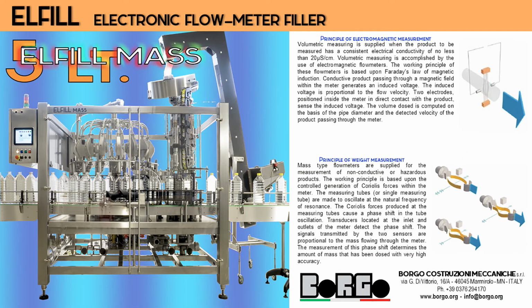Principle of electromagnetic measurement. Volumetric measuring is supplied when the product to be measured has a consistent electrical conductivity of no less than 20 microsiemens per centimeter. Volumetric measuring is accomplished by the use of electromagnetic flowmeters. The working principle of these flowmeters is based upon Faraday's law of magnetic induction.